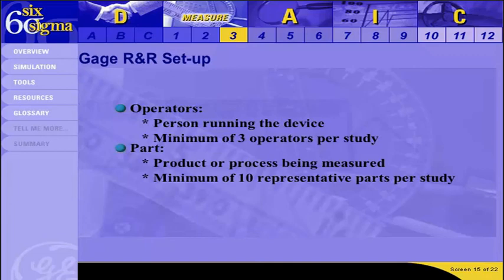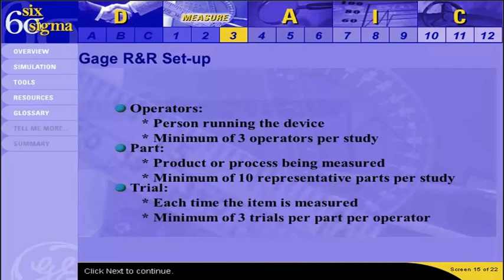There are three components to a Gauge R&R test: operators, parts, and trials. It is recommended to run the test using a minimum of three operators — the more operators, the more certainty that procedures are universally understandable. At least 10 representative parts should be provided, reflecting the range of measurements possible, and all operators must measure the same 10 parts. The trial is each time an item is measured; a minimum of three trials per part per operator is recommended, and parts should be presented in random order to avoid influencing individual measurements.